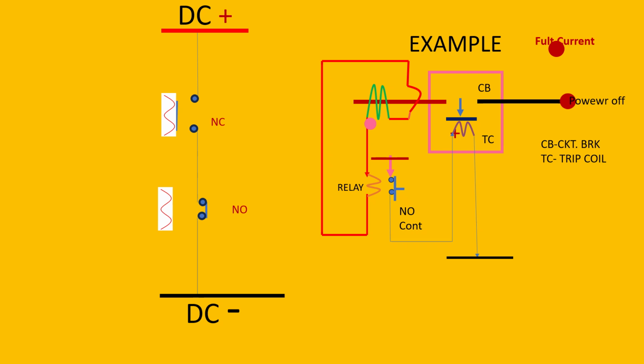This is the use of this contact. We are extending DC positive in the TRD system, and in the local control circuit also we are extending the DC positive to make a circuit, and when opening it, it will break a circuit. Here on overload, the relay coil is making the circuit breaker contact break. So we are frequently using these normally open and normally closed contacts.